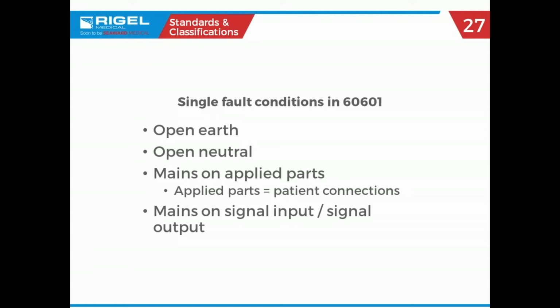And the complaint people have is, man, it has taken forever to do my safety test. Because 60601 will also say, on your EKG leads, test every lead individually to ground, and test every lead to lead to ground. So now you're coming up with 10 squared tests, and it could take 15, 20 minutes to do an electrical safety test under this standard, where if you're testing NFPA 99, you're done in under 5 minutes. I mean, it's quick.